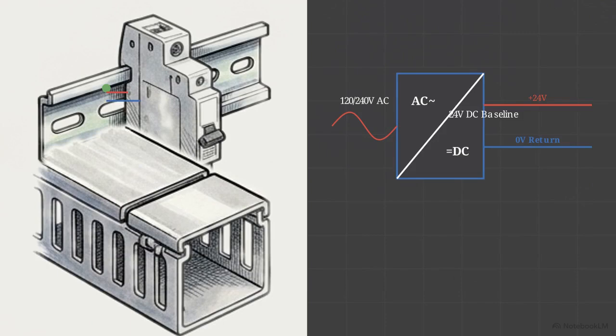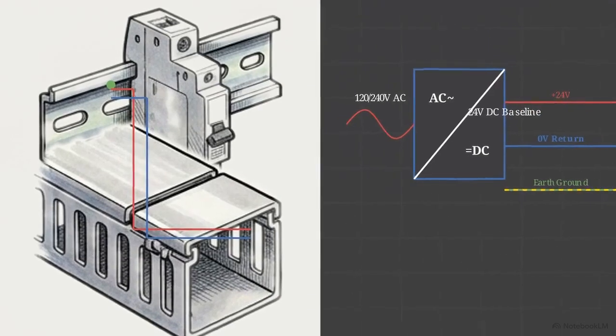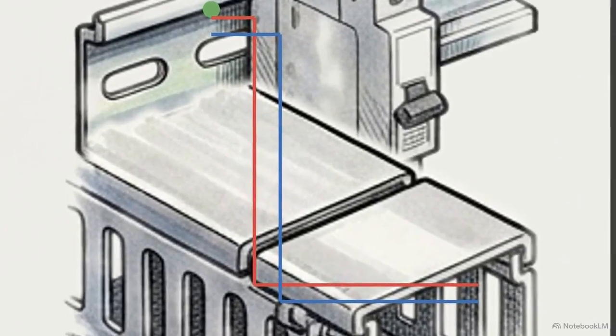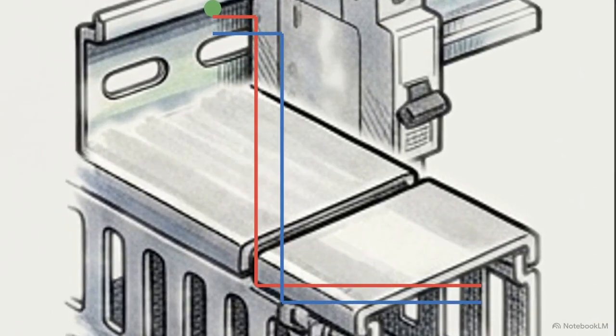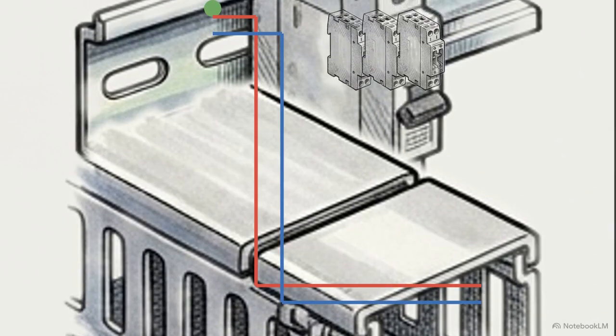From the SMPS, we draw our primary distribution bus. The red positive 24-volt line and the blue 0-volt return line must be strictly isolated across the entire schematic. We also introduce a separate dedicated earth-ground path. 0 volts is the electrical return reference for the DC circuit, while earth ground safely shunts away electromagnetic interference from the high-voltage machinery nearby. Mixing them up injects noise directly into your logic controllers.